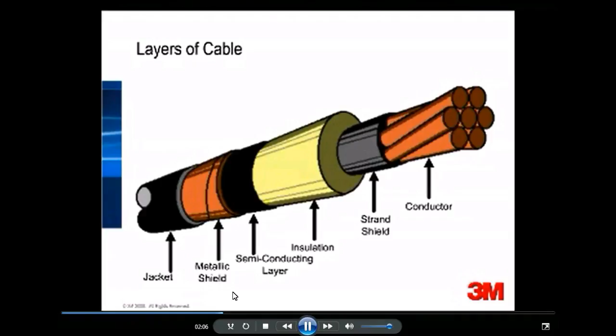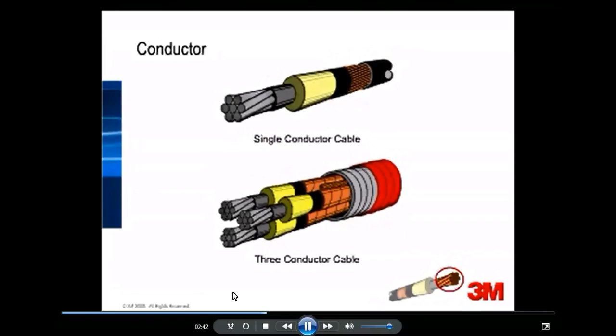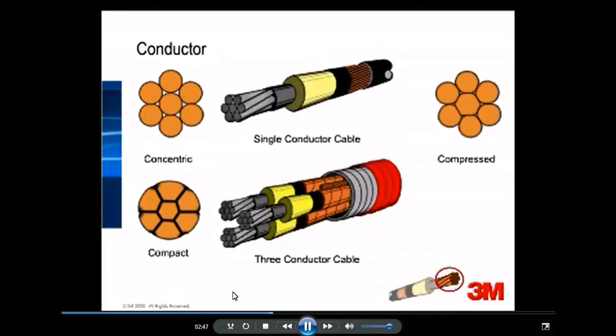There are 2 basic types of medium voltage cable, single conductor and 3-conductor cable. Single conductor cable consists of 1 conductor per cable, while 3-conductor cable has 3 individually insulated and shielded conductors. The conductor is the heart of the cable, as this is the portion of the cable whose sole purpose is to carry current. The strands that make up the conductor can be made of either copper or aluminum. Copper is generally used for industrial applications, whereas aluminum is generally used for utility applications. Conductor configurations are concentric, compressed, compact, or solid.